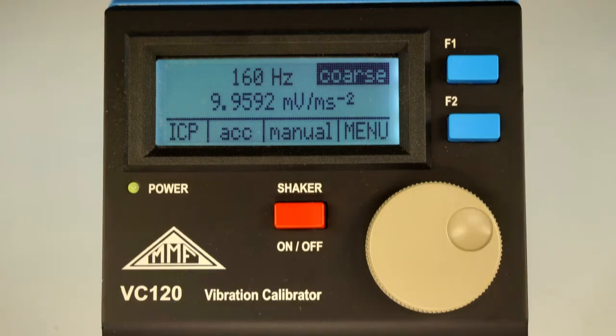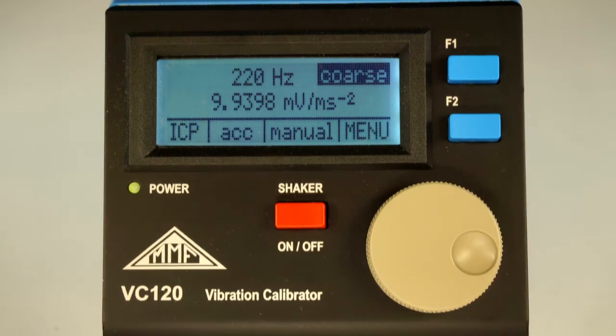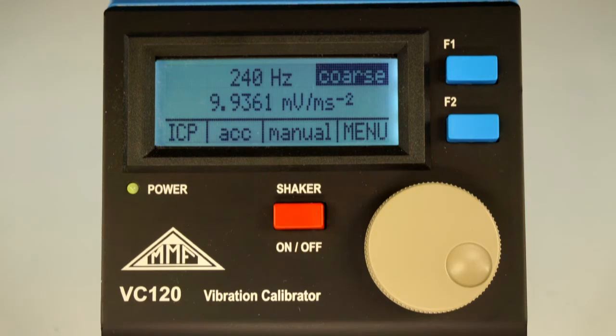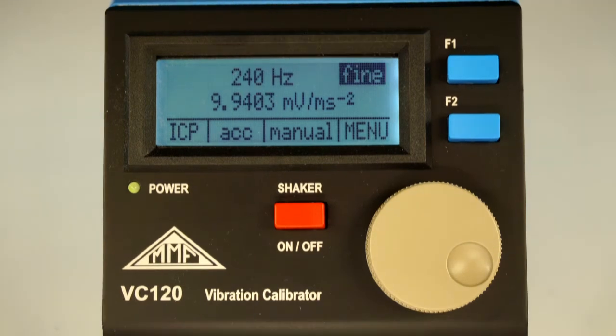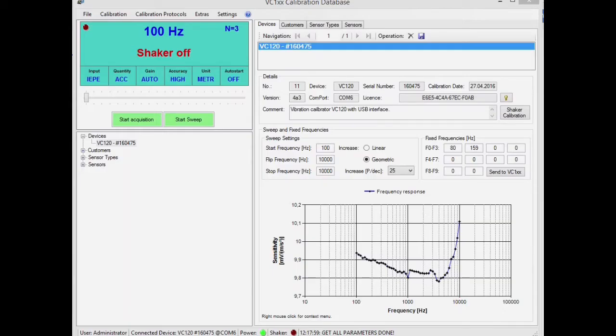By turning the shuttle wheel, you can adjust the frequency from between 70 and 10,000 Hz. The measured sensitivity appears on the display. By pressing F1 you can switch from a coarse to a finer frequency step at intervals of 1 Hz. A more convenient way to operate VC120 than via the front panel is by using the calibration database. With the calibration software, you can also carry out frequency sweep measurements.